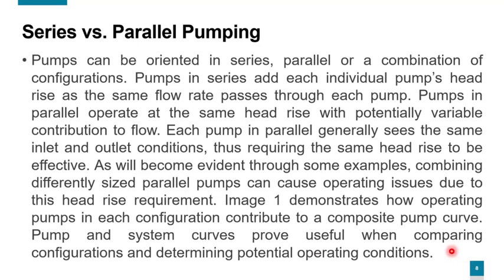Series versus parallel pumping. Pumps can be oriented in series, parallel, or a combination of configurations. Pumps in series add each individual pump's head rise as the same flow rate passes through each pump. Pumps in parallel operate at the same head rise with potentially variable contribution to flow. Each pump in parallel generally sees the same inlet and outlet conditions, thus requiring the same head rise to be effective, as will become evident through some examples.